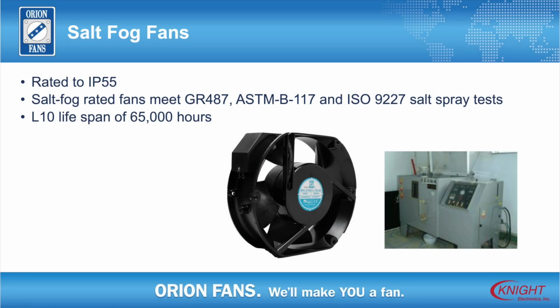Tested in tough environmental conditions, these AC and DC fans are subjected to salt fog, salt spray, temperature changes, and humidity. Compliant with international standards on salt spray tests GR 487, ASTM B117, and ISO 9227, these IP55 rated fans meet or exceed accelerated salt spray and salt fog testing, lasting from 8 to 3,000 hours, providing maximum resistance to corrosion.